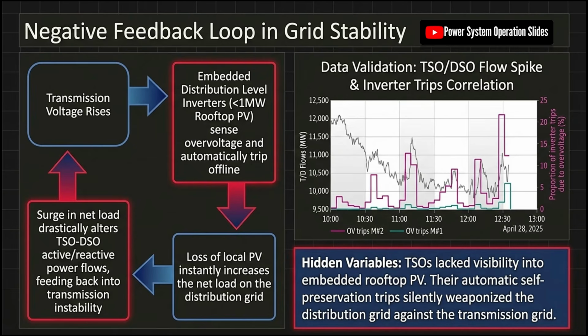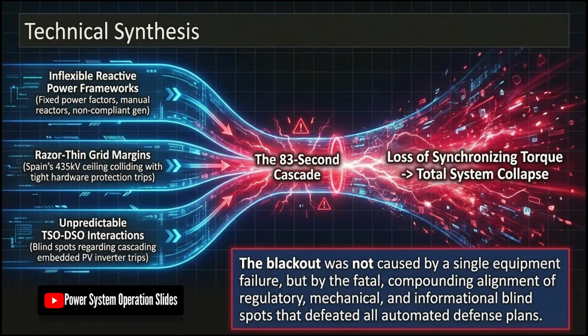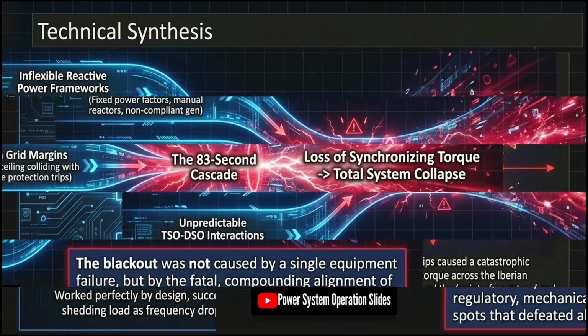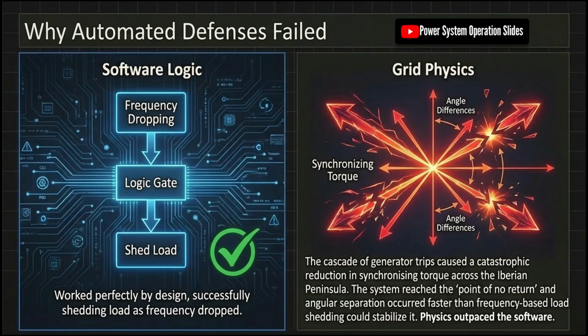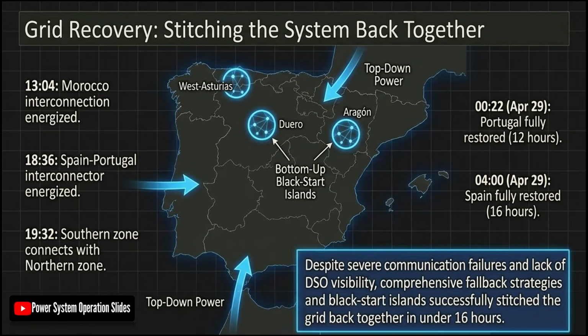This process, known as cascading failure, can ultimately lead to system separation, widespread load shedding, voltage collapse, frequency collapse, and complete blackout. A critical aspect of blackout risk is the balance between generation and demand, which directly determines system frequency. Insufficient generation, loss of major generating units, low operating reserves, or reduced system inertia can cause rapid frequency decline and trigger under-frequency load shedding or generator protection actions.